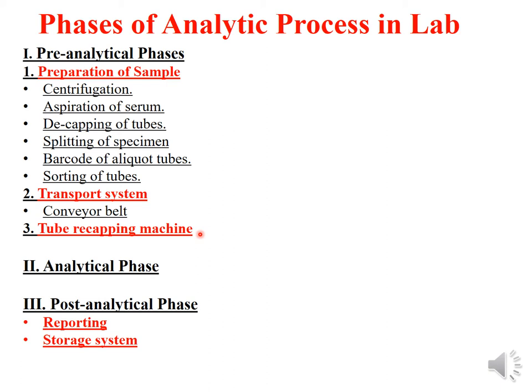The third pre-analytical step is a tube recapping machine, where once the aliquots are taken in the sample cups the tubes are capped again. We then come to the second phase — the analytical phase — where the testing or analysis of the sample is carried out.